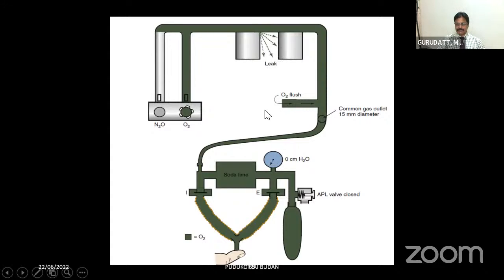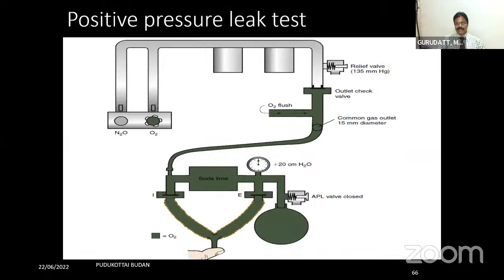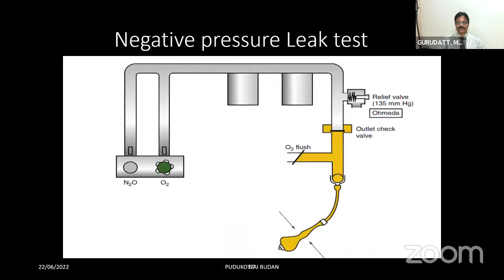But this positive pressure leak test can only be done for Draeger machines where there are no check valves. If there are outlet check valves, you are checking the leak only from the check valve downwards. So if there is a leak in the vaporizers or in the flow meters, you will not be able to check. So in the case of GE machines, you should always go for the negative pressure leak test.